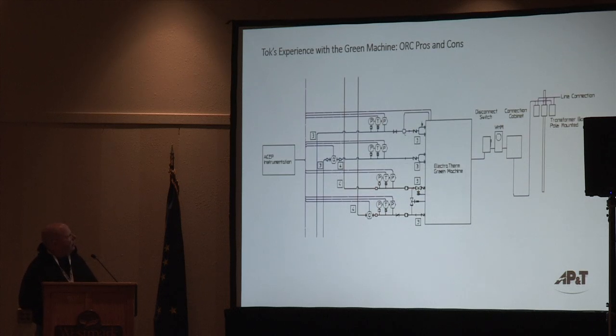This is a portion of the detail that shows the Electratherm installation. It's got the same red and blue lines, plus it has the purple lines that show the control and sensor connections that ACEP installed to monitor the performance of the ORC. And it shows the connection onto the grid. We go from the Electratherm machine with 480 volts out into the yard up to a pole mounted transformer set and raise the voltage to transmission level.